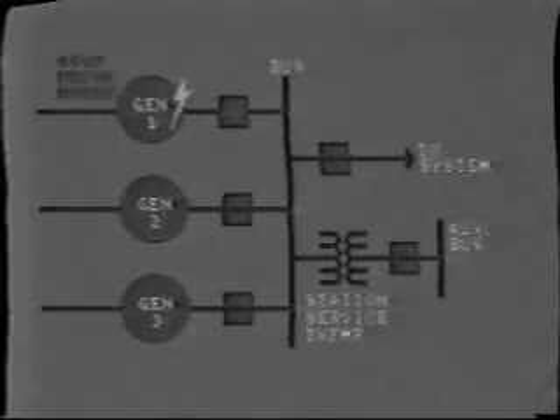Another type of internal fault is the ground fault on the rotor, that is, the field windings. Now, this is not such a serious problem as the rotor operates at a relatively low DC voltage, about 500 volts, compared with the stator winding voltage of, say, 15 kV or more. Moreover, the rotor winding is ungrounded, so there is no path for flow of ground fault current. For this reason, a ground fault on the rotor will not call for immediate tripping, but rather the need to schedule a convenient outage for inspection of the generator. We'll be looking at rotor ground detection later in this tape.